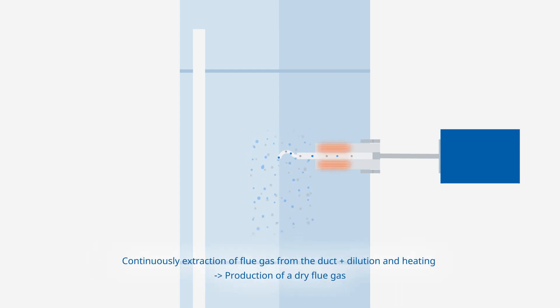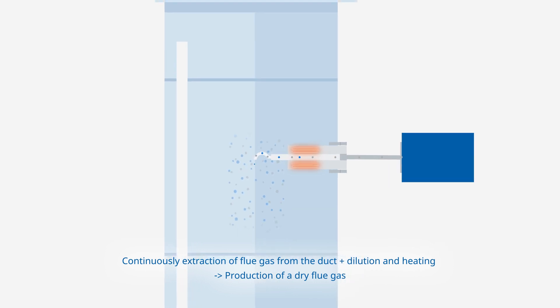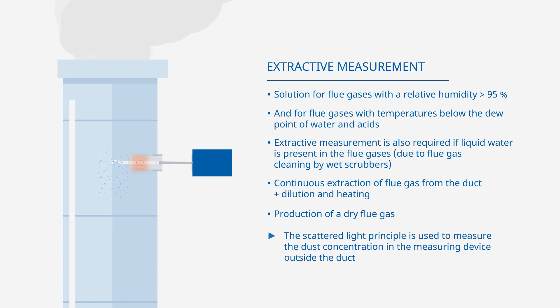For extractive measurement, the flue gas is continuously extracted from the duct by a probe, diluted and heated. This produces a dry flue gas. The scattered light principle is used to measure the dust concentration in the measuring device outside the duct.